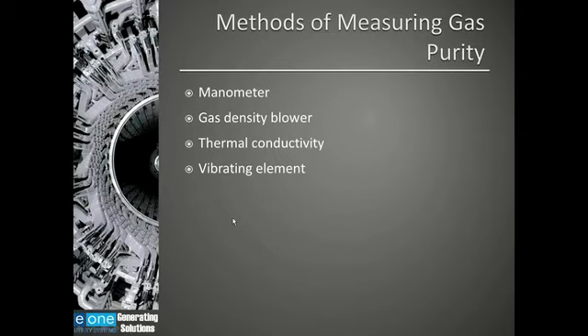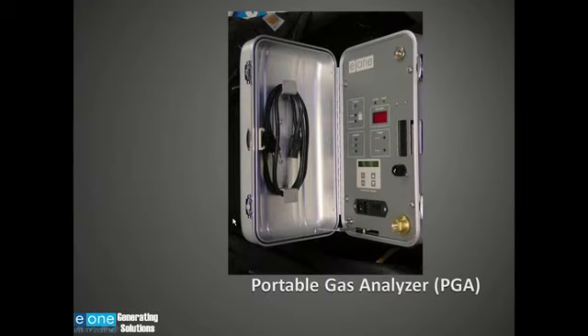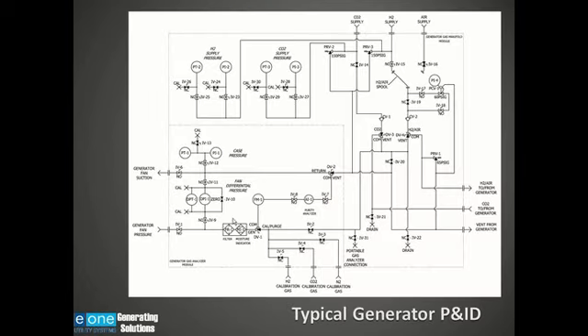This is a picture of that portable analyzer that I mentioned earlier, and that some power plants like to use these to provide a redundant signal during the purging process. This analyzer is not rated to be used in a hazardous area, so it should be used in a well-ventilated, safe area. Here, I just wanted to point out the portable gas connection again, and you'll note that the portable gas analyzer is on the same line as the permanently installed analyzer.